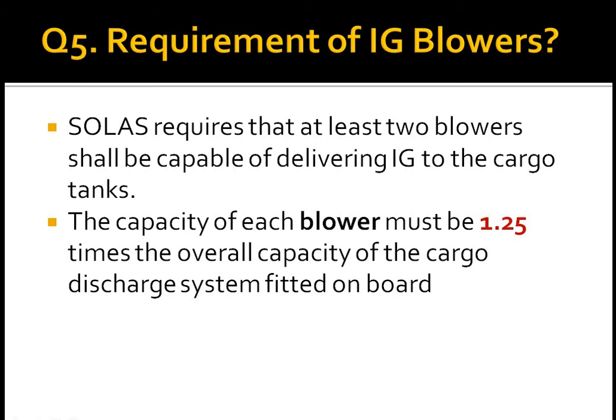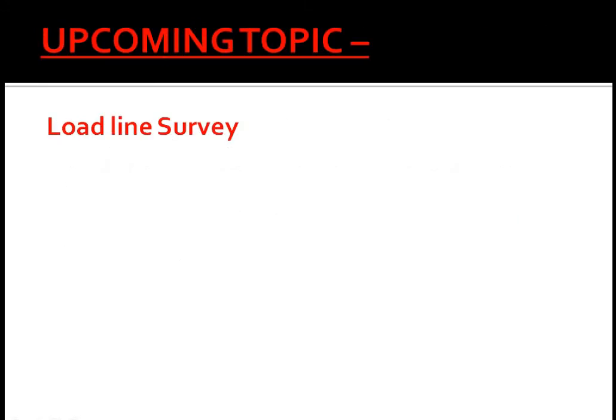Question 5: requirements of IG blowers. SOLAS requires that at least two blowers shall be capable of delivering inert gas to the cargo tanks. The capacity of each blower must be 1.25 times the overall capacity of the cargo discharge system fitted on board.